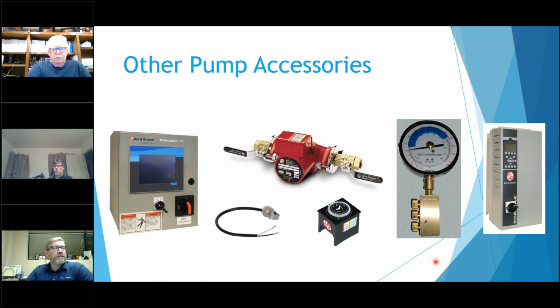You've got pressure gauges, of course. Always good to have those so you can troubleshoot the pump. We've got little isolation flanges. These are great for these small booster pumps. A lot of times we go out there and don't even see shutoff flanges around the pump, and inevitably that's the one that has something wrong with it, or the pump's not working properly, and you have to drain the whole system. Whereas if you have these, you lose just a small amount of water. Most of the flanges are built in, so it makes it pretty easy to install the pump as well.